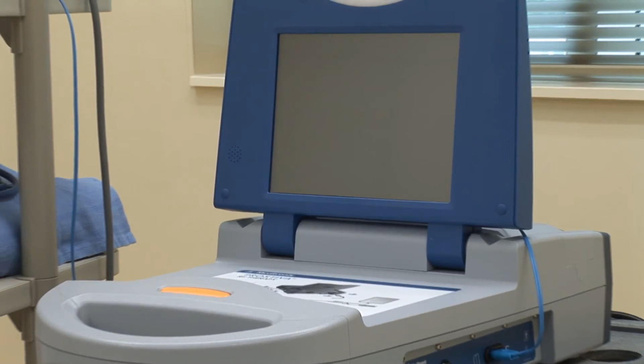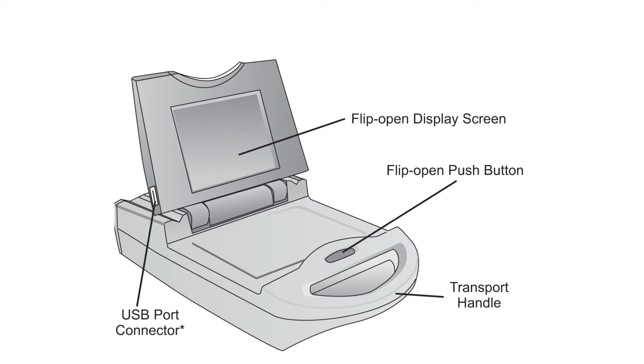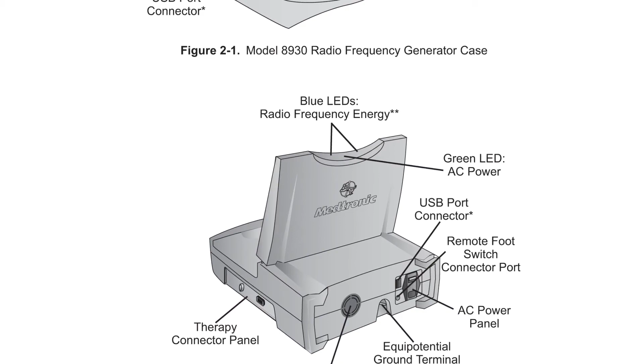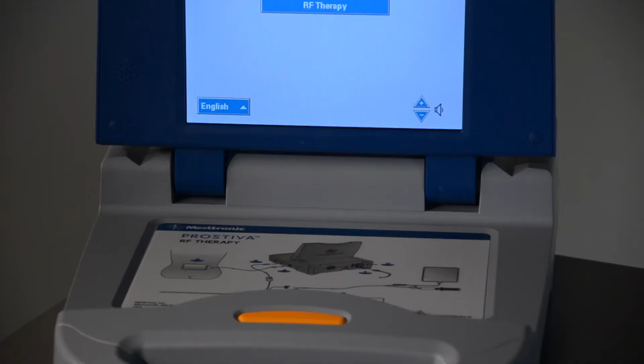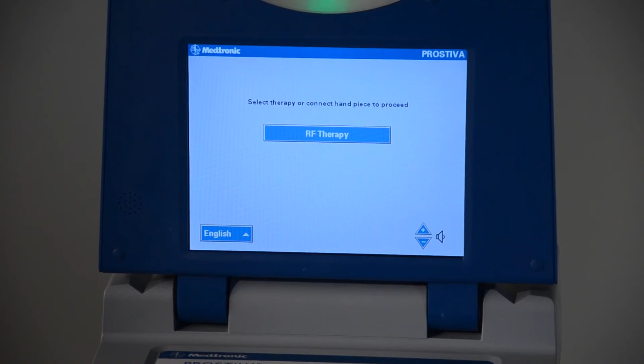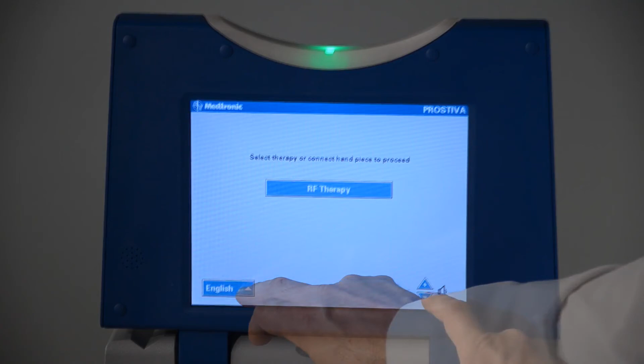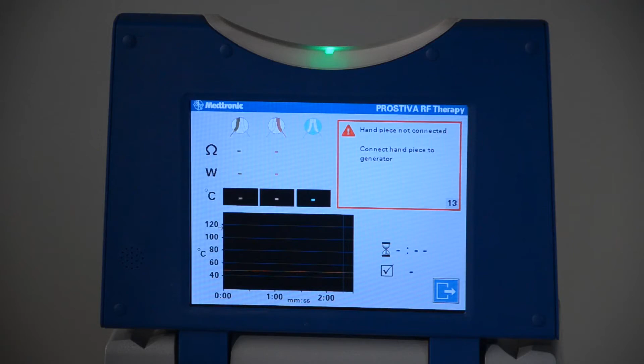The generator should be placed on a steady table. The rear panel should not be blocked to allow for airflow. The latch button opens the display screen. The power cable connector and power switch are located at the back of the device. The return electrode cable connects to the RF generator. After the unit is turned on, a startup display screen appears. There are several language options to choose from, and adjustments can be made to the volume tones. There are a number of message codes that can be displayed, as well as several safety, warning, and cautionary messages.